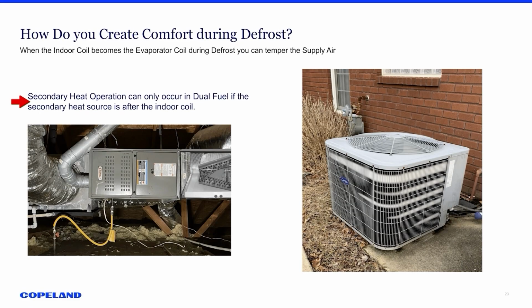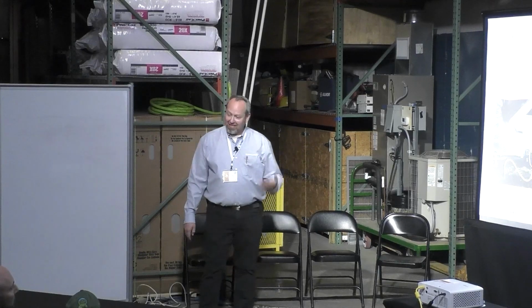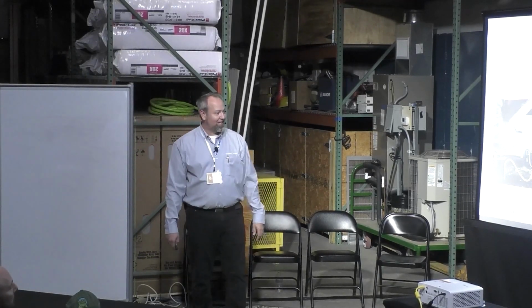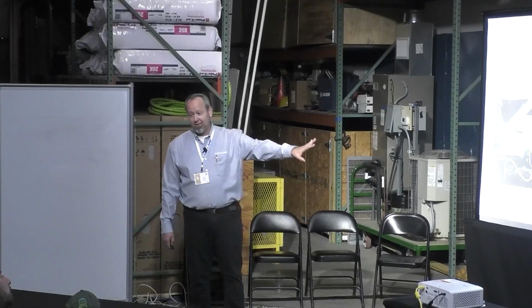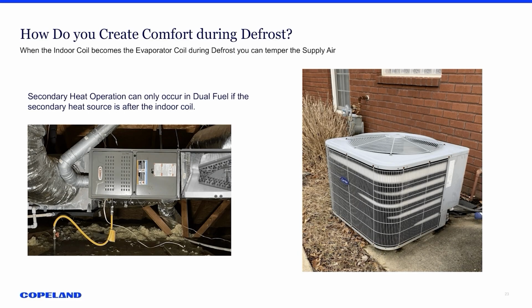Let's hit the defrost cycle and the backup heat a little bit here while we're at it. Again, that secondary heat can only occur in dual fuel if that coil is before the heat. The benefit is that during defrost, you can now turn on that additional heat. By the way, don't look at these installs. They're pretty awful. I'm going to go on to the next slide here.